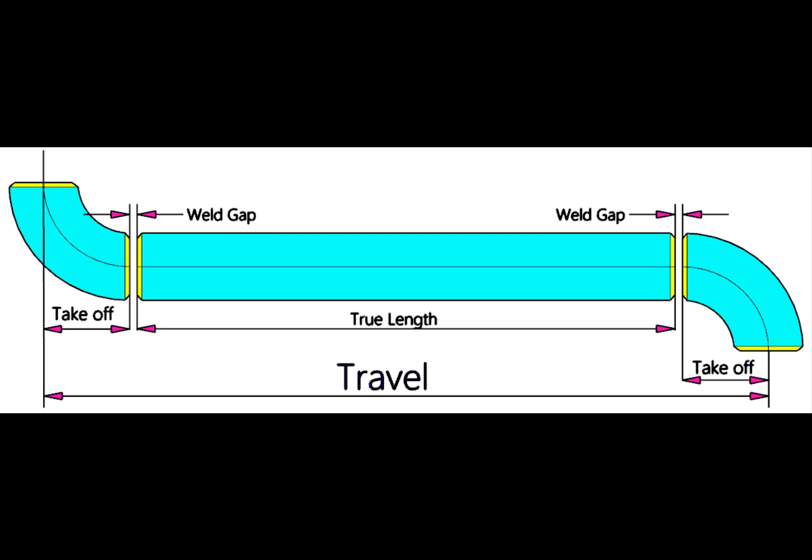So how will we calculate the true length of the spool? The true length or cut length is: add 2 welding gaps and 2 take offs, then minus this sum from the travel.